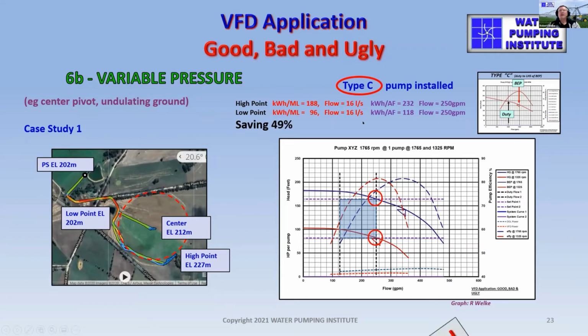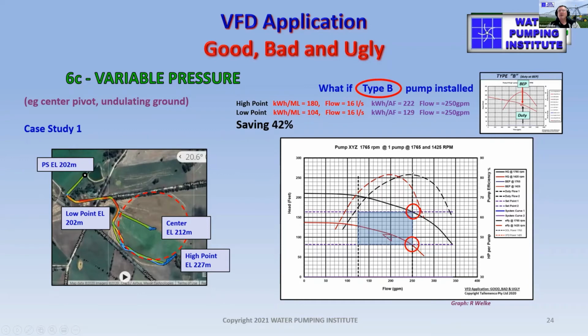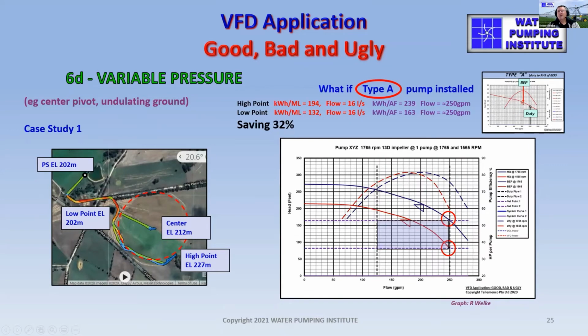But what if we had a type B pump? So a type B pump would start up here, best efficiency, and then finish up at a lower efficiency. And the savings in this particular case is only 42%. What if we went for a type A pump, where the duty is to the right-hand side of the best efficiency point? Now, bear in mind, this is more than likely the most likely pump you'll find in the field. And this one spells disaster, really. So you start off with an efficiency point that's already falling on the right-hand side, and you drop the head down at that same flow rate, and so you're down to 60%. So that's a particularly ugly situation. You would not want to use a type A pump on this particular application, which is variable pressure, constant flow.